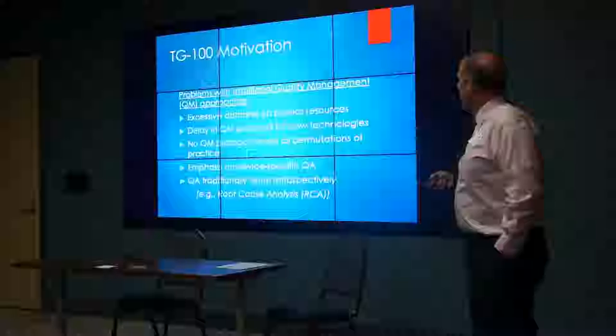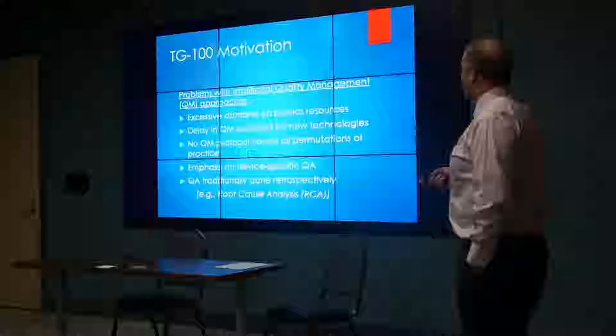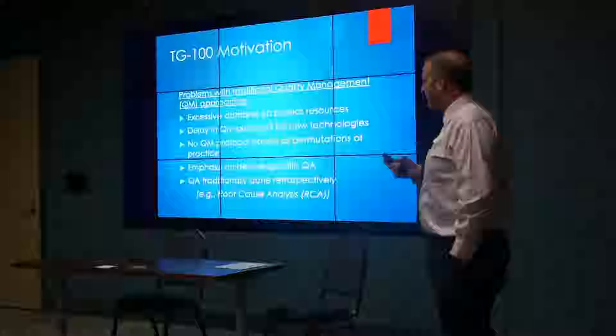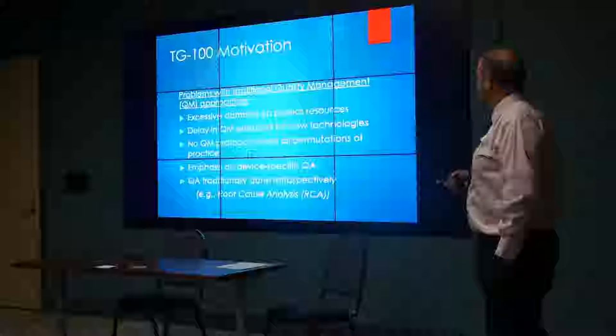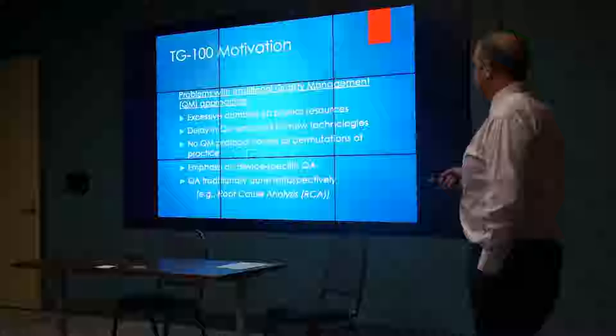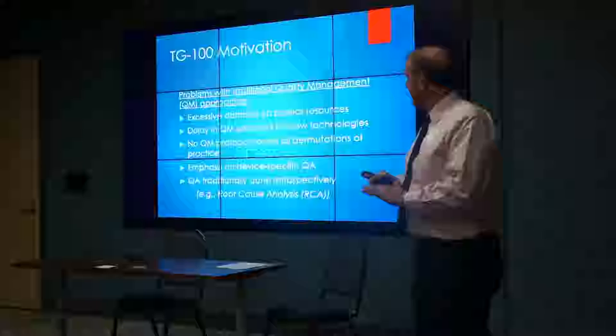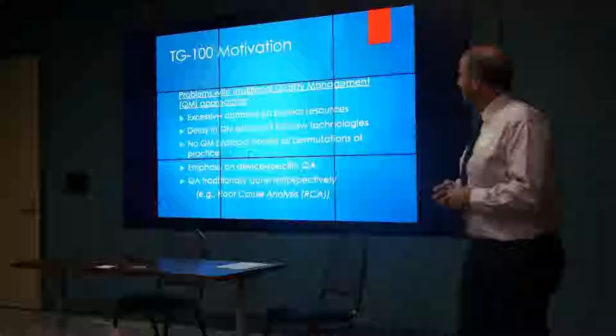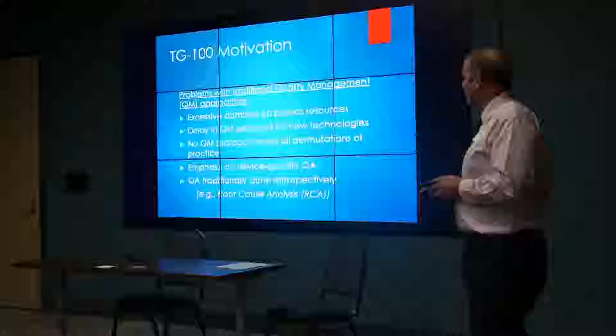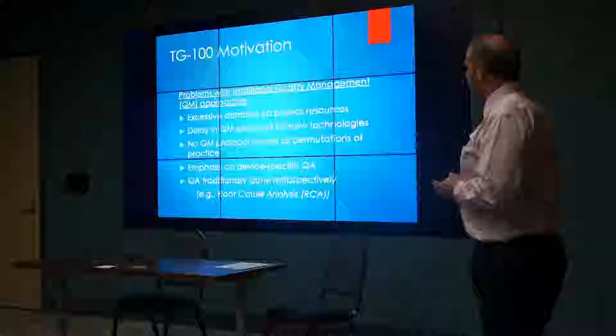What is the motivation for this new approach? There are several problems with traditional quality management approaches such as TG-40 or TG-142. One is an excessive demand on physics resources—modern technologies are very complex, with lots of components, and physicists are strapped to do QA on all of these devices. A lot of times it's not necessary if those devices are not used in the way that the quality assurance measurement is testing. There's also a delay in quality management protocols—when task groups are created, it sometimes takes years before they produce a report.